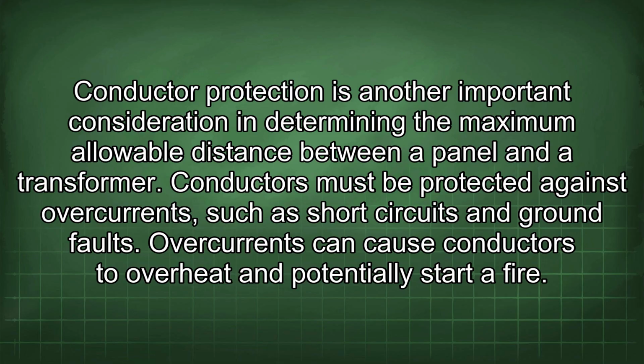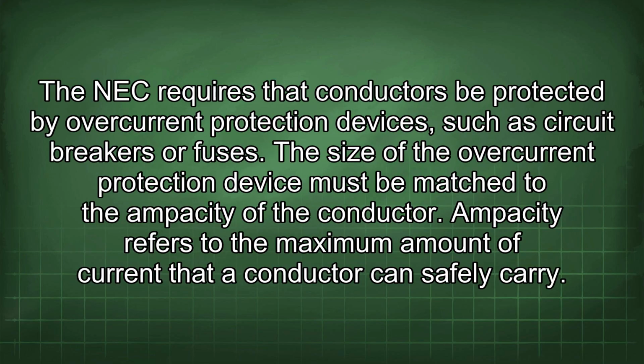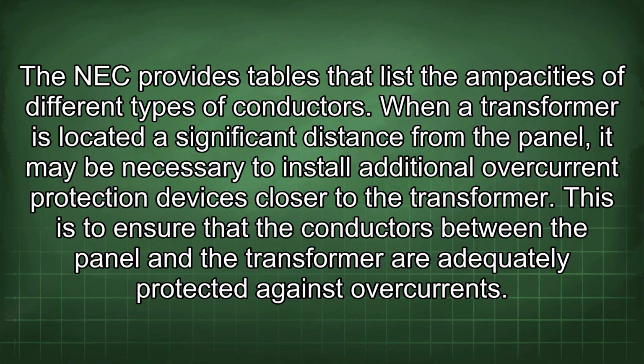Conductor protection is another important consideration in determining the maximum allowable distance between a panel and a transformer. Conductors must be protected against overcurrents, such as short circuits and ground faults. Overcurrents can cause conductors to overheat and potentially start a fire. The NEC requires that conductors be protected by overcurrent protection devices, such as circuit breakers or fuses. The size of the overcurrent protection device must be matched to the ampacity of the conductor. Ampacity refers to the maximum amount of current that a conductor can safely carry. The NEC provides tables that list the ampacities of different types of conductors.